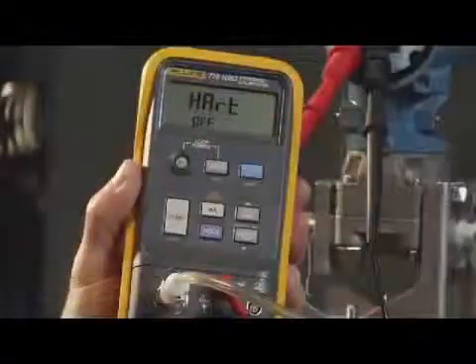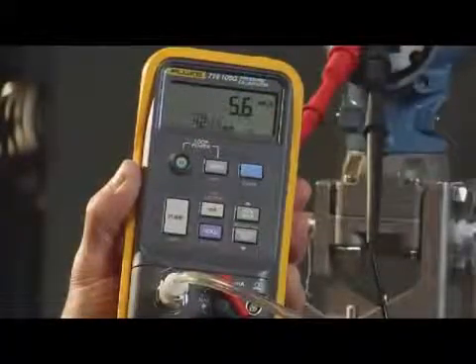Power up the transmitter with the loop power supply. We'll measure the milliamp signal drawn from the power supply that is provided by the 719. Initially we see the milliamp signal being measured and the pressure that's being applied.